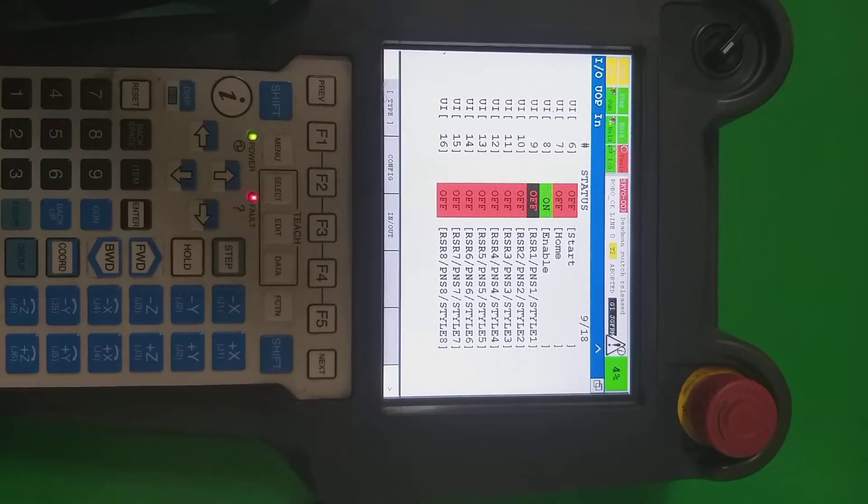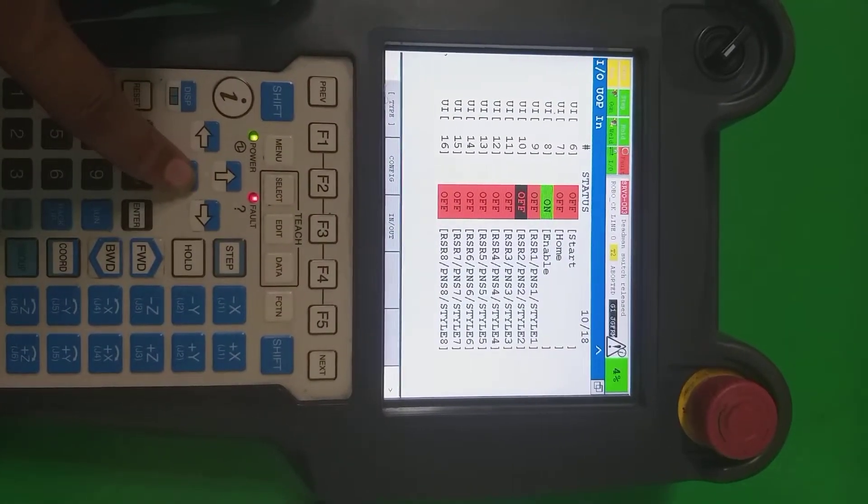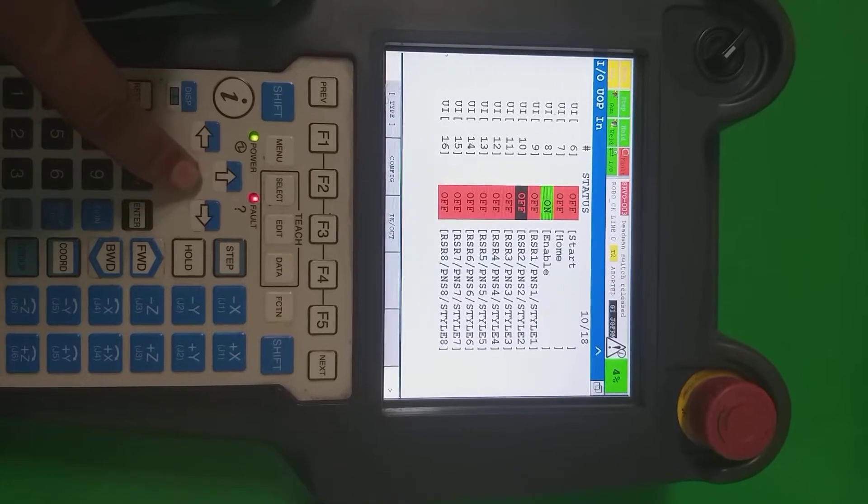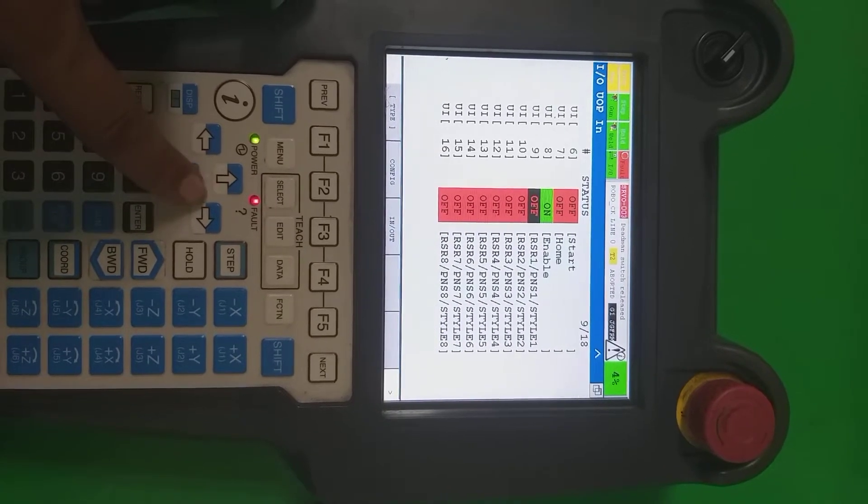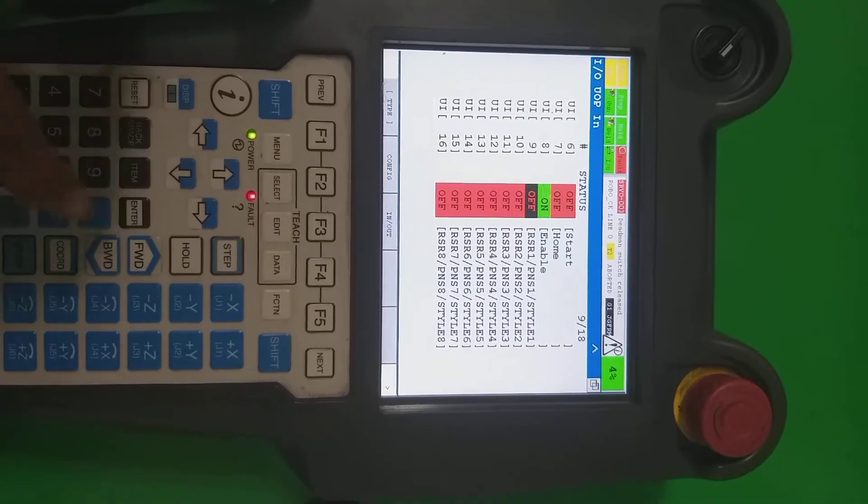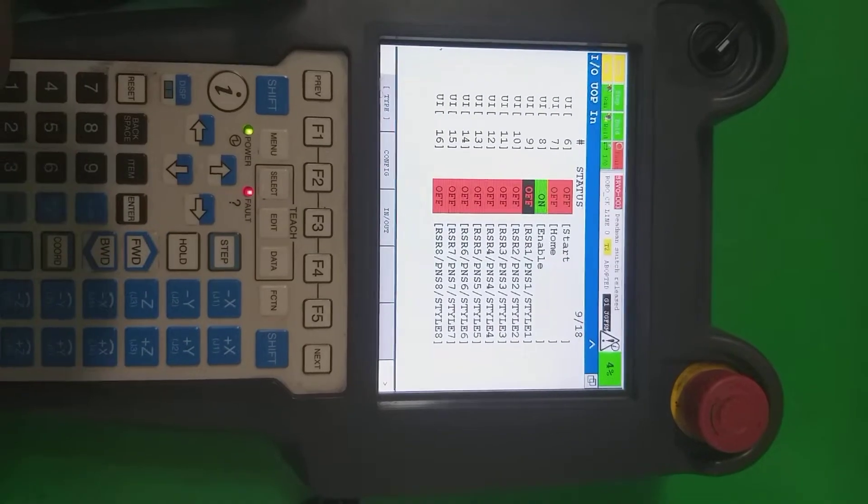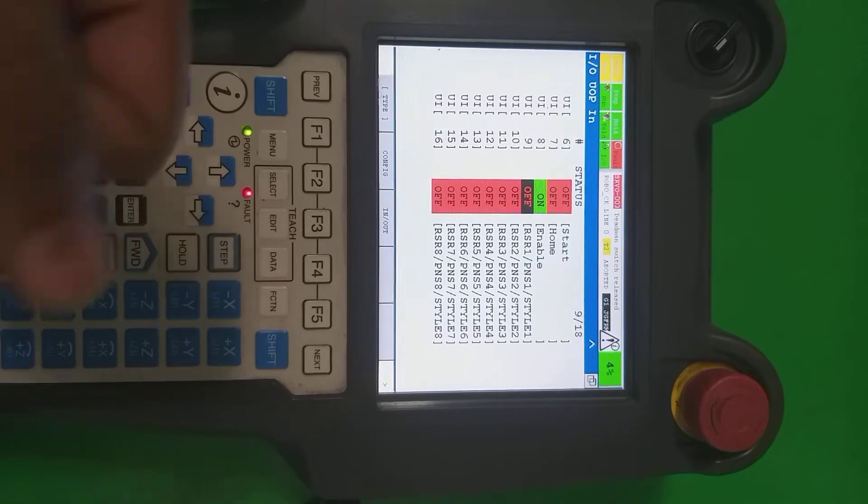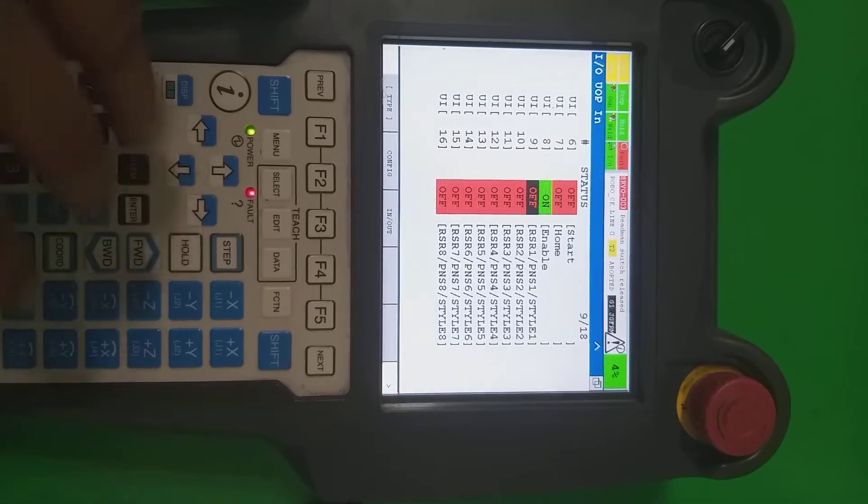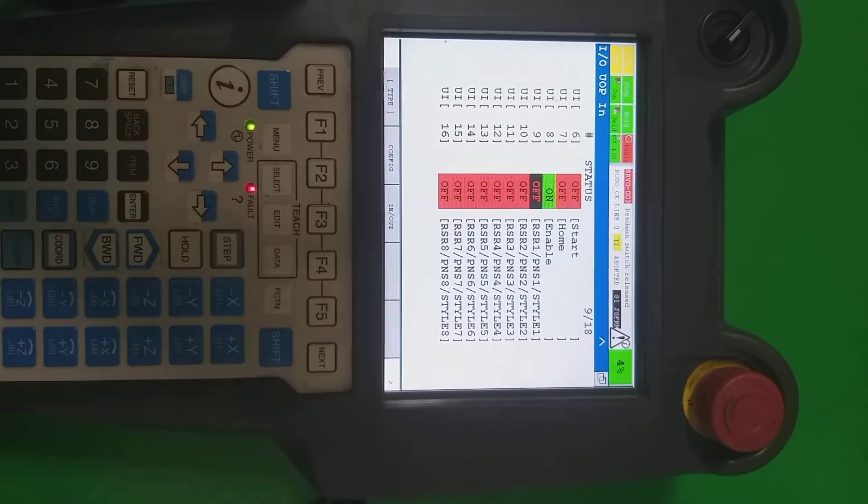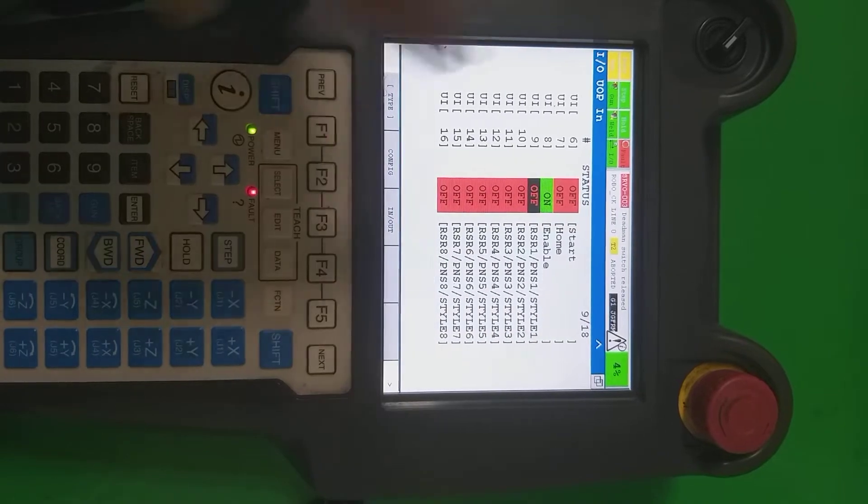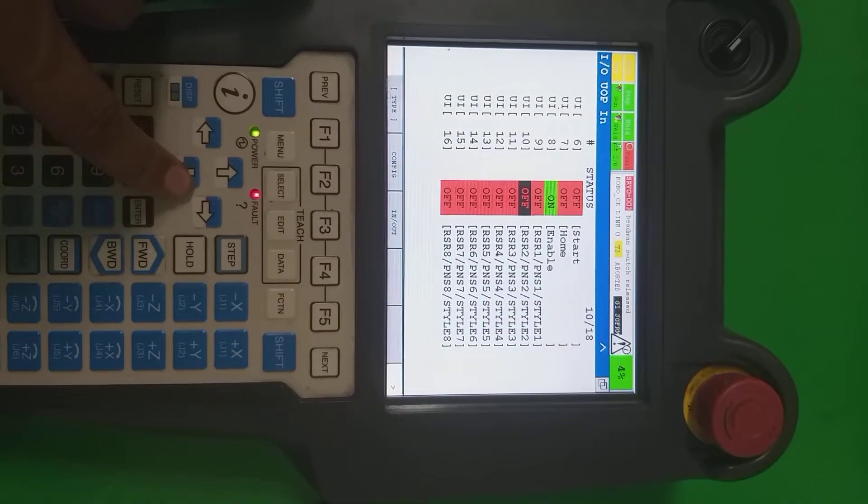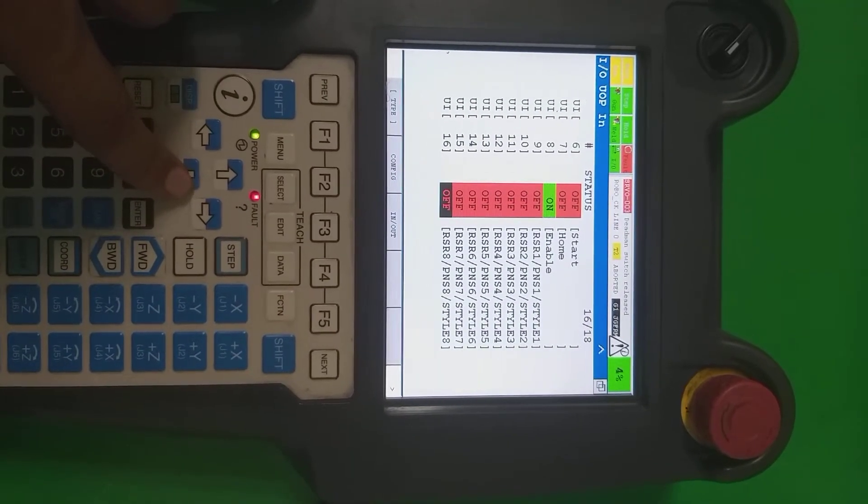What are these actually? All upper conditions going to be healthy and our robot in automat, all things are okay. That time PLC gives one this input number on. If it's making nine number on, that means it calls automatically the program RSR1. If RSR is not there, it calls automatically the PNS1. If PNS is not there, that time it calls automatically style1.